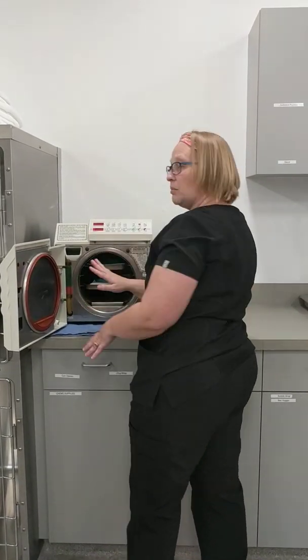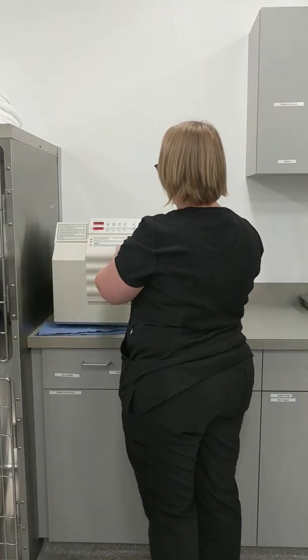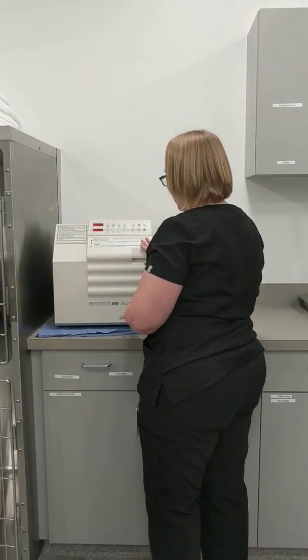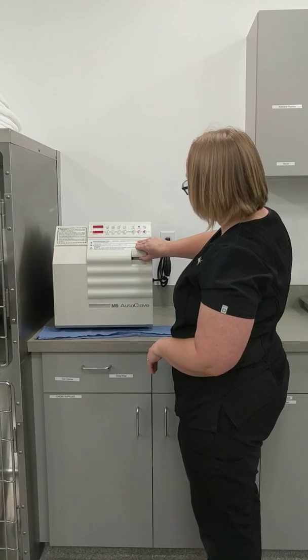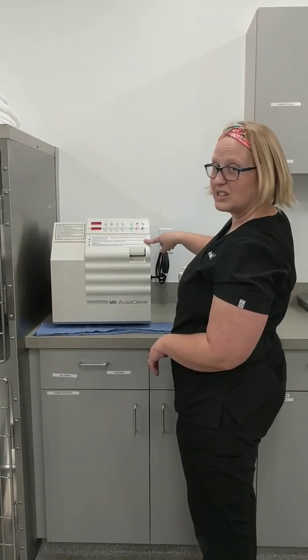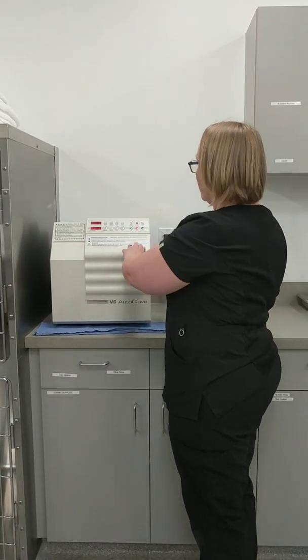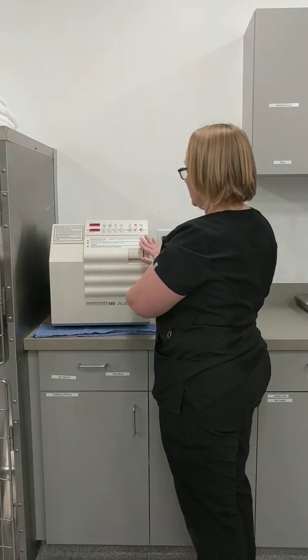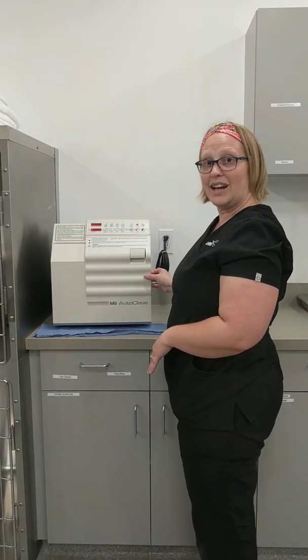Once these are in, I'm going to shut this door, ensuring that it is completely locked. This lever, if it is sticking up like this, you can see that door can still jiggle. That's not all the way shut. You need to make sure this is locked down in order to create that nice firm seal.